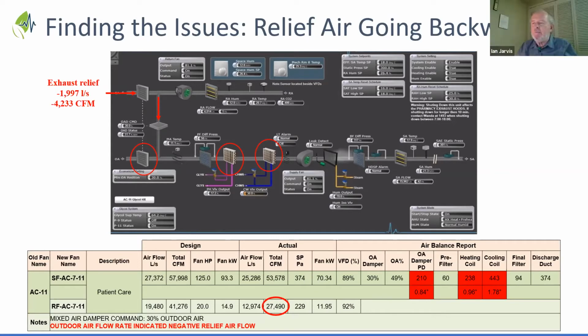And we're reminded, Amandeep, of the power of a fan. Anybody who's opened the access door on the suction side of a fan knows very well those things are beasts. They will not be denied. So if the supply fan is looking for more air than the return air fan is bringing back, it doesn't matter what you set your minimum outside air setting at. Those numbers are completely meaningless because it's going to get that air from somewhere. If it's not coming back through the system, it's coming either from the outside air or the relief air intake damper, because it will not be denied. That supply air volume will be satisfied.